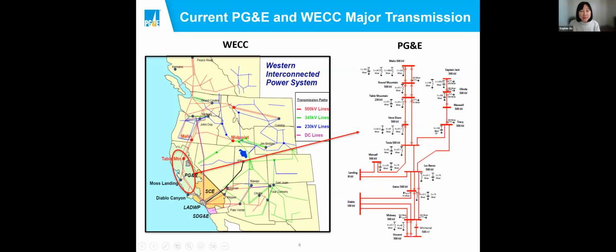And just a rough idea about how closely connected the system is. I did just a rough measurement from the top north substation to the bottom south substation. It's about 500 miles. And in between these 500 miles, we have 3 parallel lines, and basically in that distance, we have about 7 substations in between. So then you can imagine the average length of the 500 kV transmission lines. And with those 500 kV transmission lines, you also have series compensation of about 60 to 70%. So mostly PG&E's reliability issue on transmission right now is thermal issue because of the close connection.